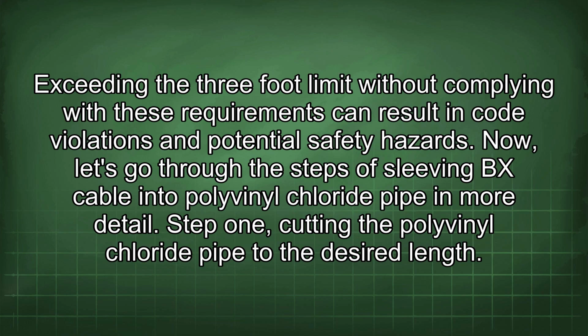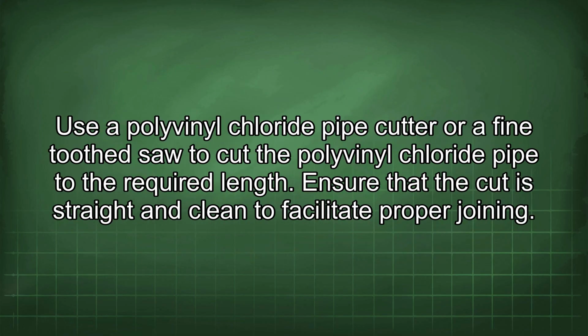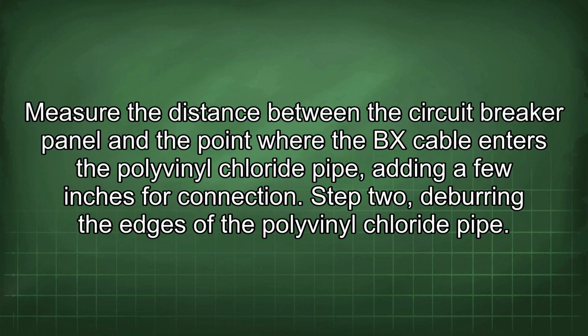Step 1. Cutting the polyvinyl chloride pipe to the desired length. Use a polyvinyl chloride pipe cutter or a fine-toothed saw to cut the polyvinyl chloride pipe to the required length. Ensure that the cut is straight and clean to facilitate proper joining. Measure the distance between the circuit breaker panel and the point where the BX cable enters the polyvinyl chloride pipe, adding a few inches for connection.